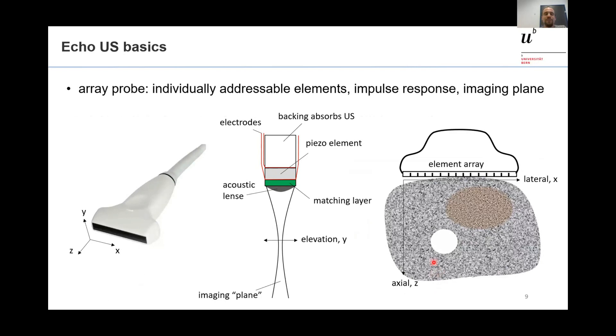For those not familiar with echo ultrasound imaging: typically we have a linear array probe with a line of piezoelectric elements. The x-coordinate is parallel to the array, the z-coordinate is the axial direction into the tissue, and the y-direction is perpendicular to the imaging plane. From the side, the piezoelectric element has an acoustic backing, matching layers, and an acoustic lens, which focuses or collimates the ultrasound into the imaging plane.